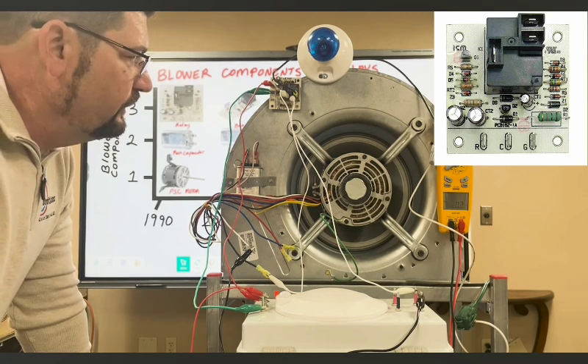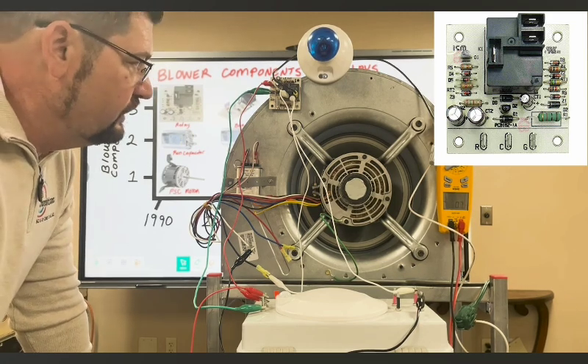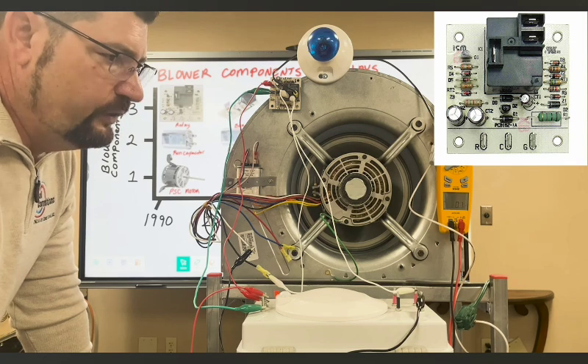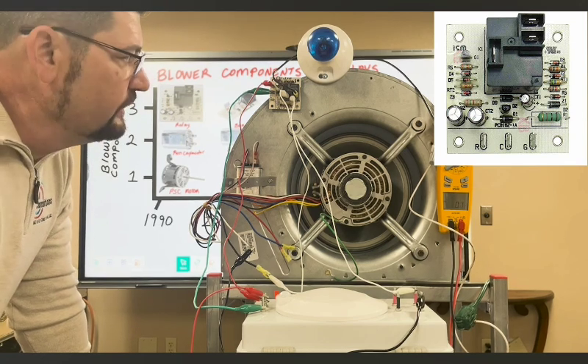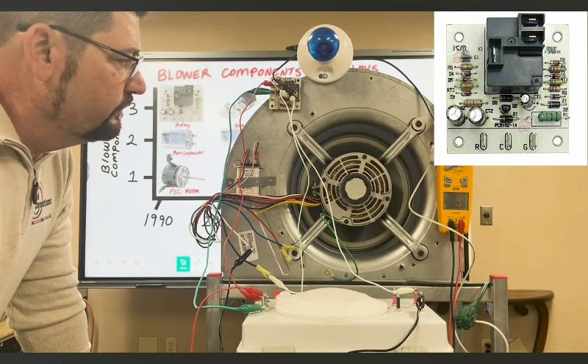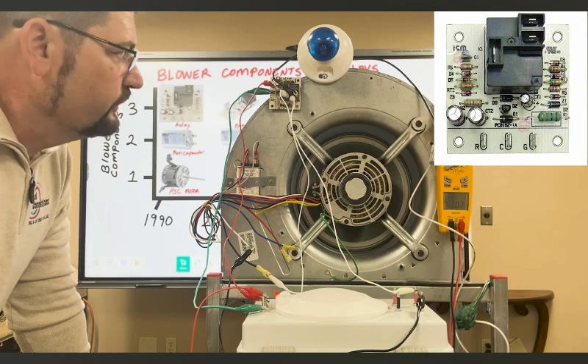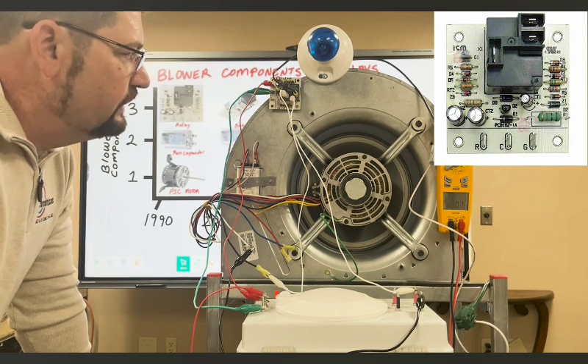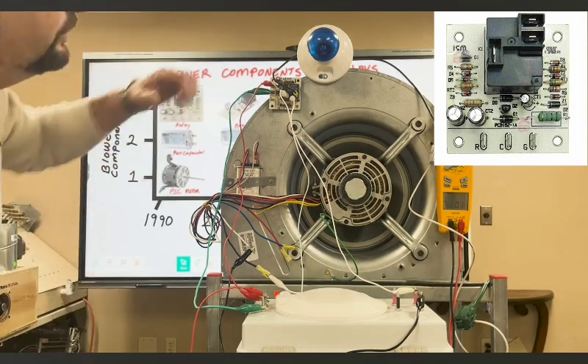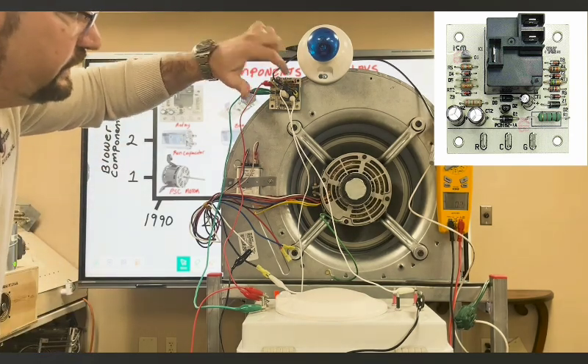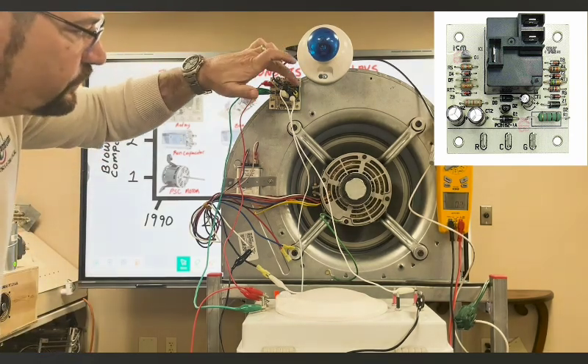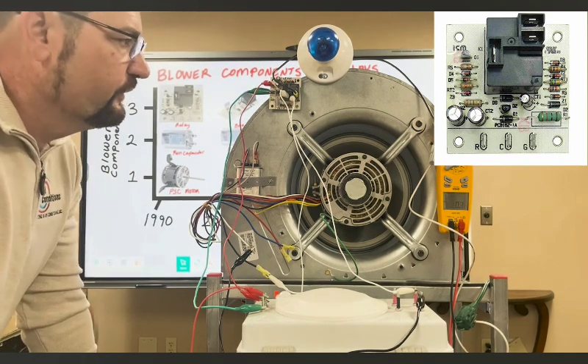And so what happens is you can easily misdiagnose this, because when it typically fails, it fails in the closed position, and the fan motor does not shut off. And we can diagnose it with a meter very simply by seeing, between the common and the normally open or normally closed terminal, where voltage is present.